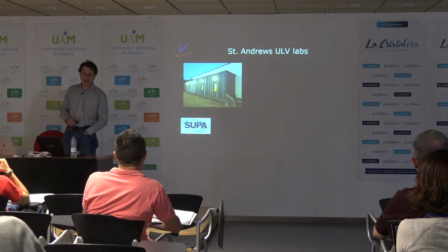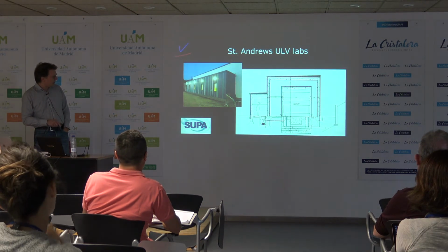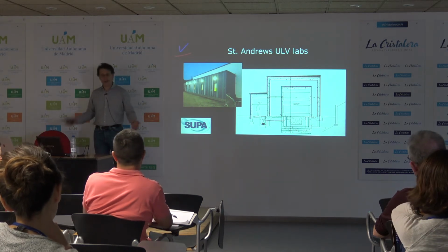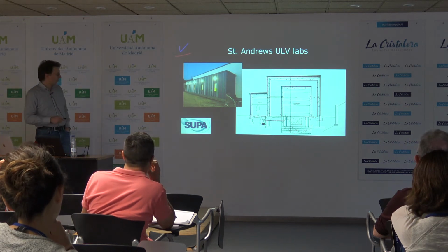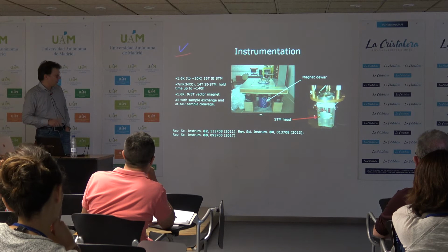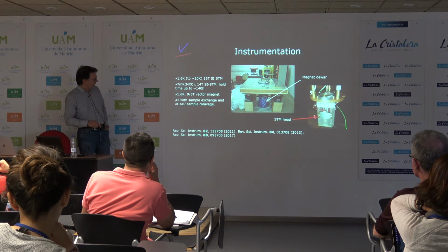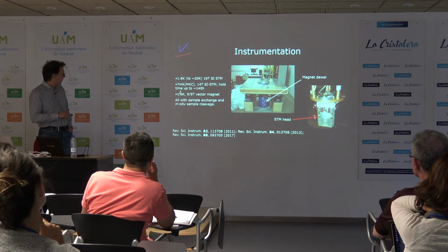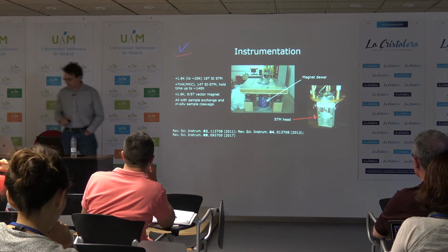So this is, if you like, our ship here. This is the ultra low vibration labs in St. Andrews, where we have our scanning tunneling microscopes. They all sit on concrete blocks which are isolated from the floor and which sit inside acoustic enclosures to basically minimize any impact of vibrations or of acoustic noise. And the instruments we operate are all home-built. They sit in commercial magnets, and then the microscope heads are made out of sapphire because it has a very high stiffness and a high thermal conductivity. And we currently operate 3 of them, 2 of them at 1.6 Kelvin, and one sits in a dilution refrigerator.